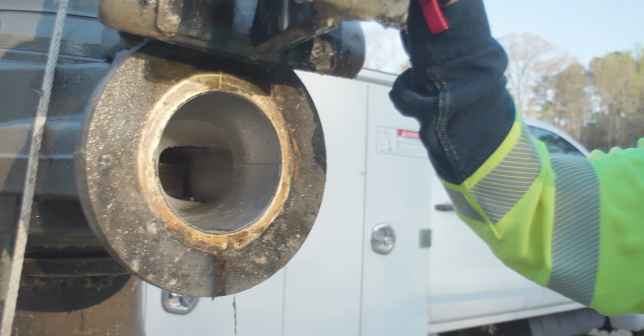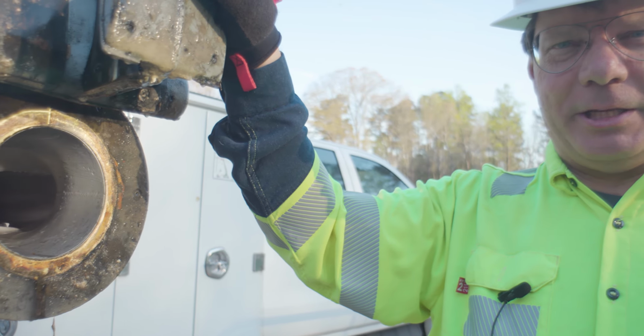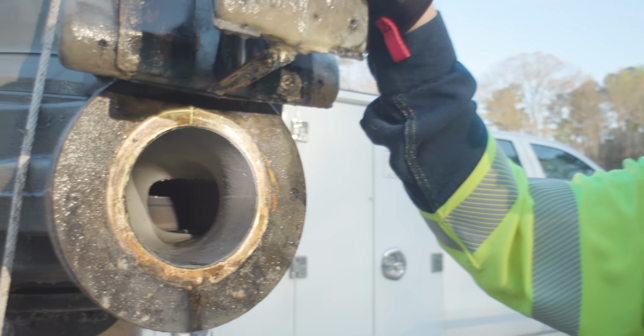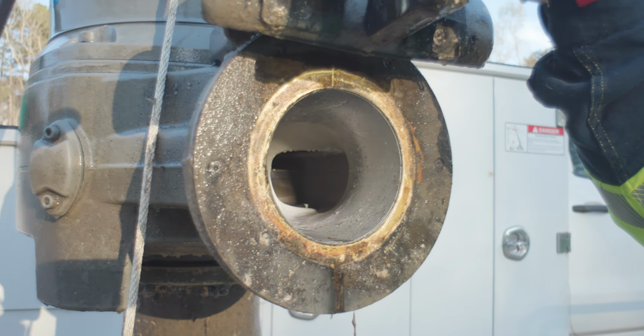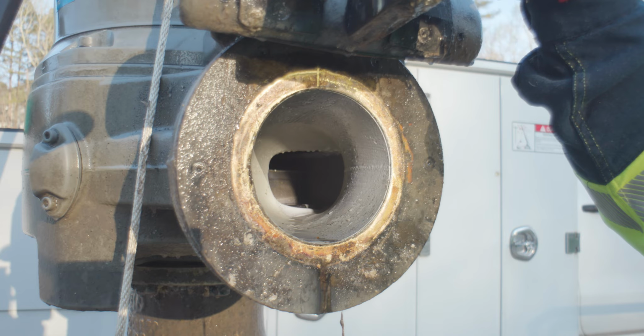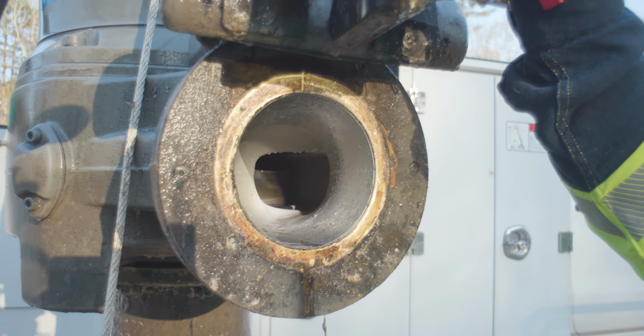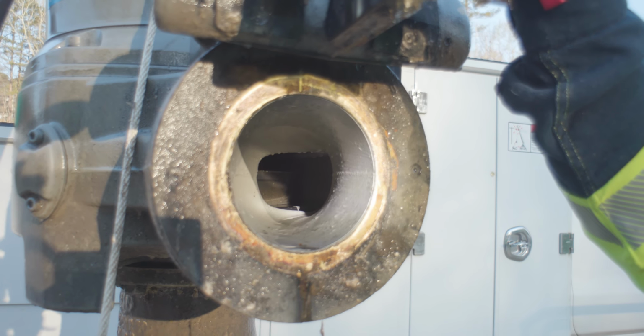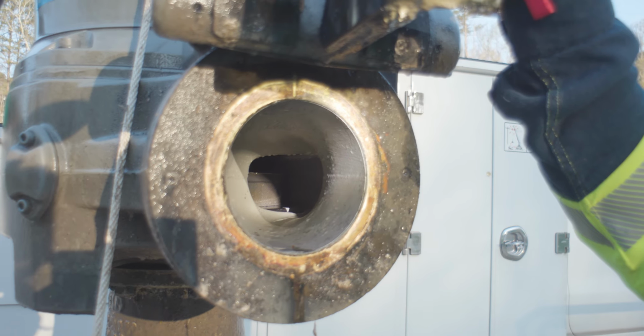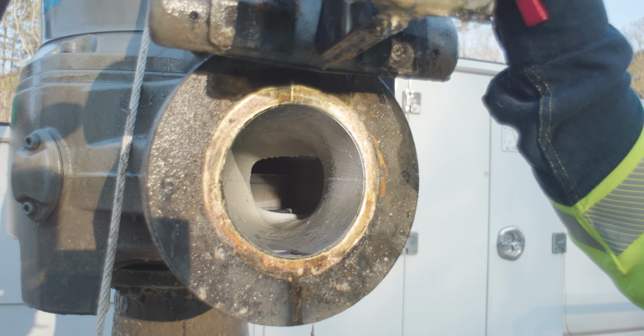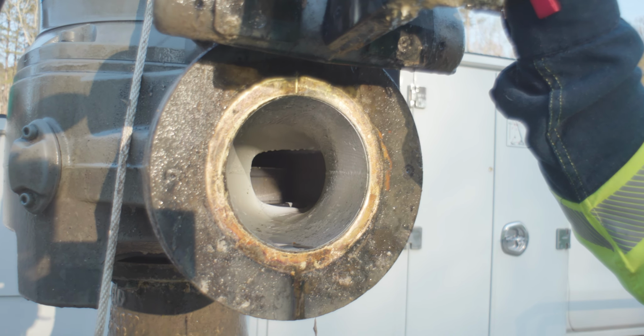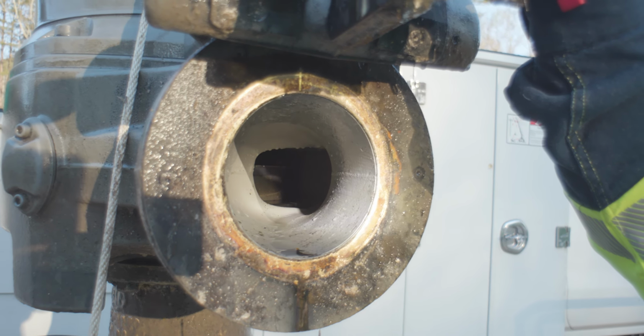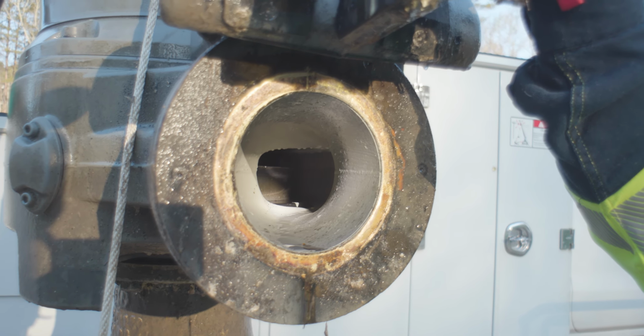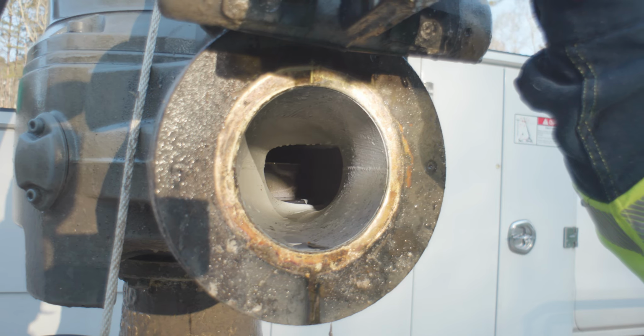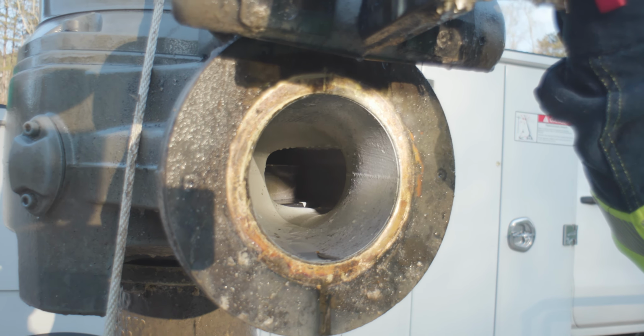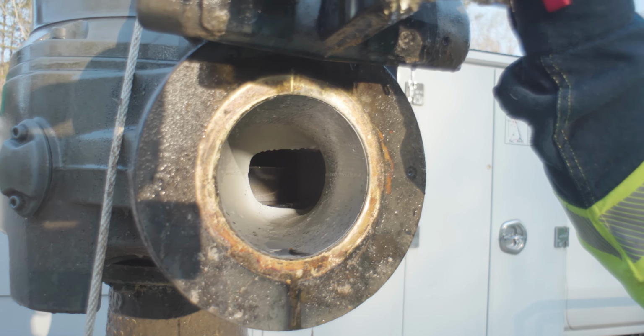We're going to be going over the adjustment of the impeller. What you're looking at is looking through the discharge of the pump. You can see where the impeller sits near the bottom insert ring, and we're going to be adjusting that to about 0.5 millimeter using a 14 and a 17 millimeter Allen wrench. We'll go over that procedure, but you're not going to be able to actually see it. So we're showing what we're adjusting in advance.